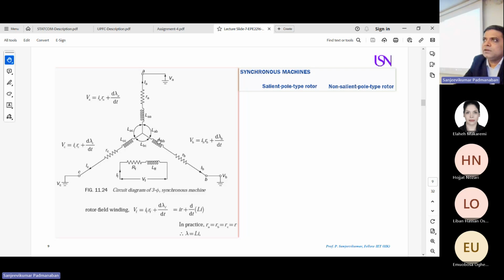For example, the phase impedance of the first winding, say 10 ohms, the second phase will have 9.9 ohms, the third phase will have 9.2 ohms. This deviation will make a big difference in the voltage because we are not measuring the voltage on a small scale, but in megawatts, megavolts, MVA. So a small deviation multiplied by MVA is big.